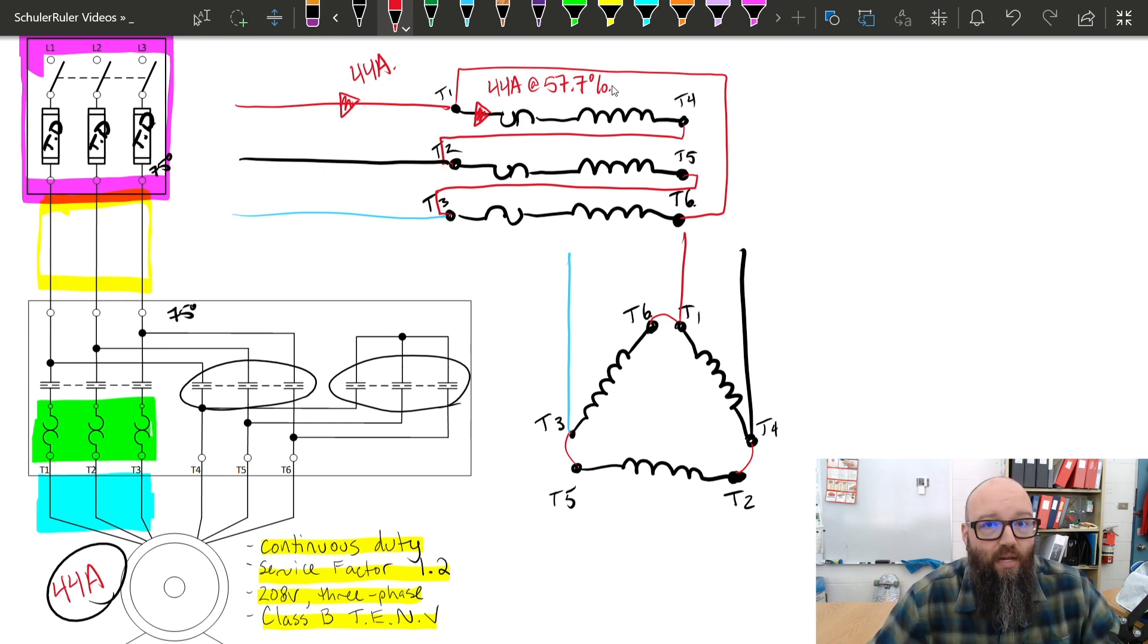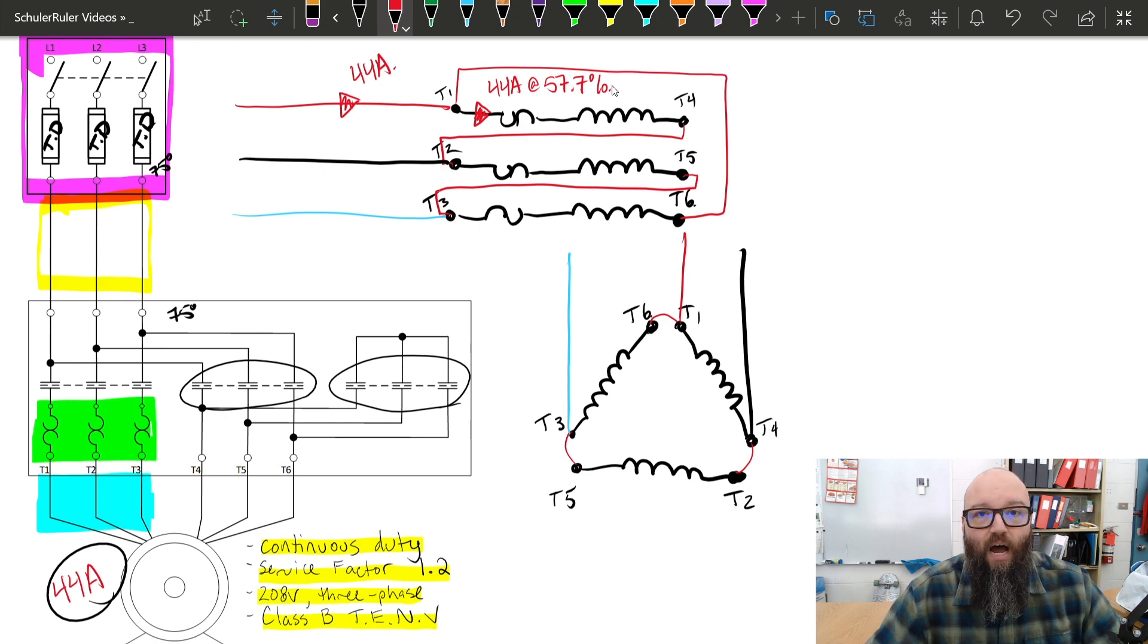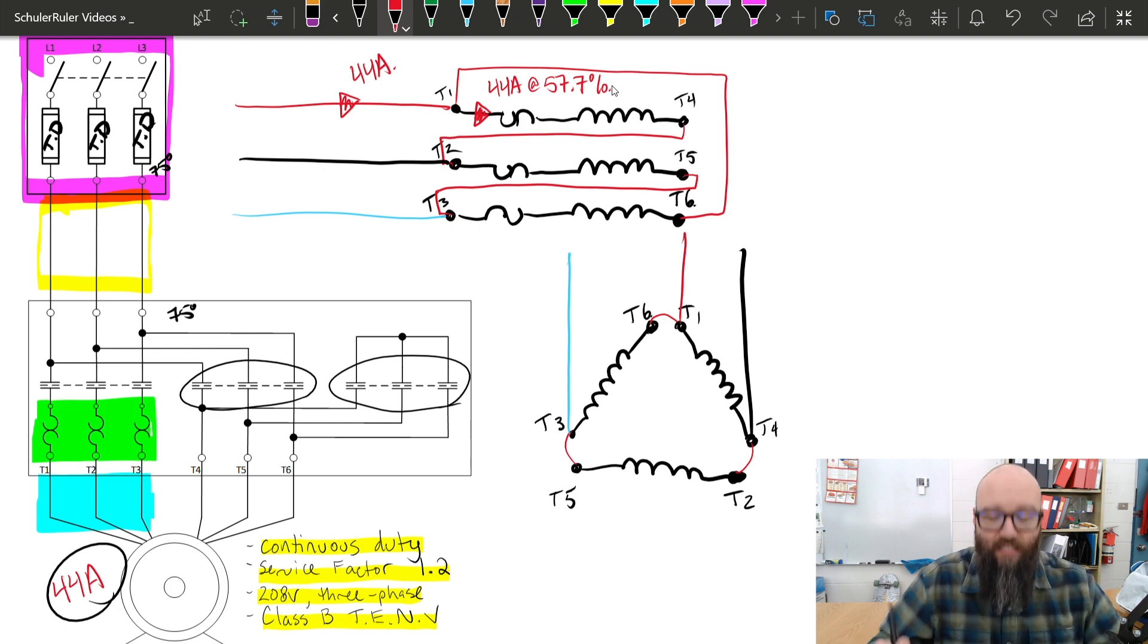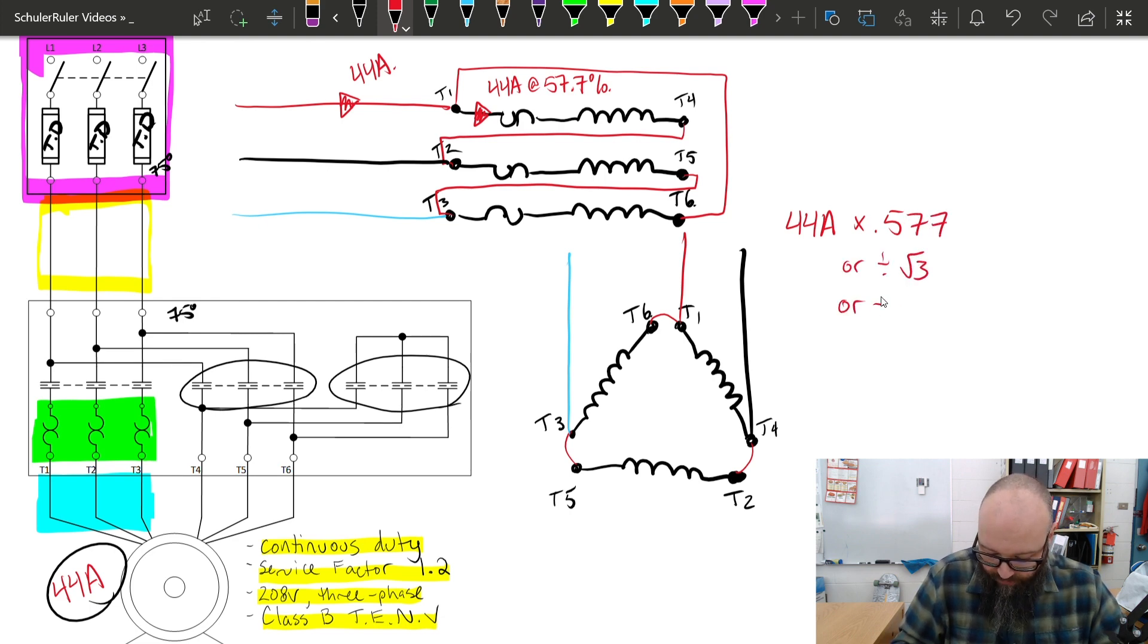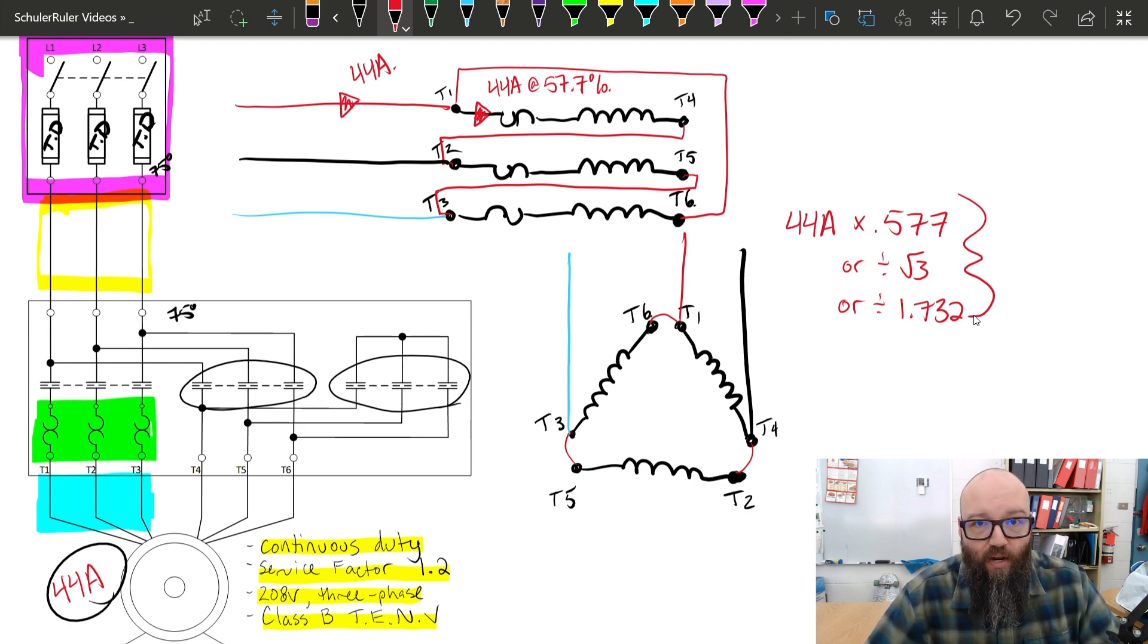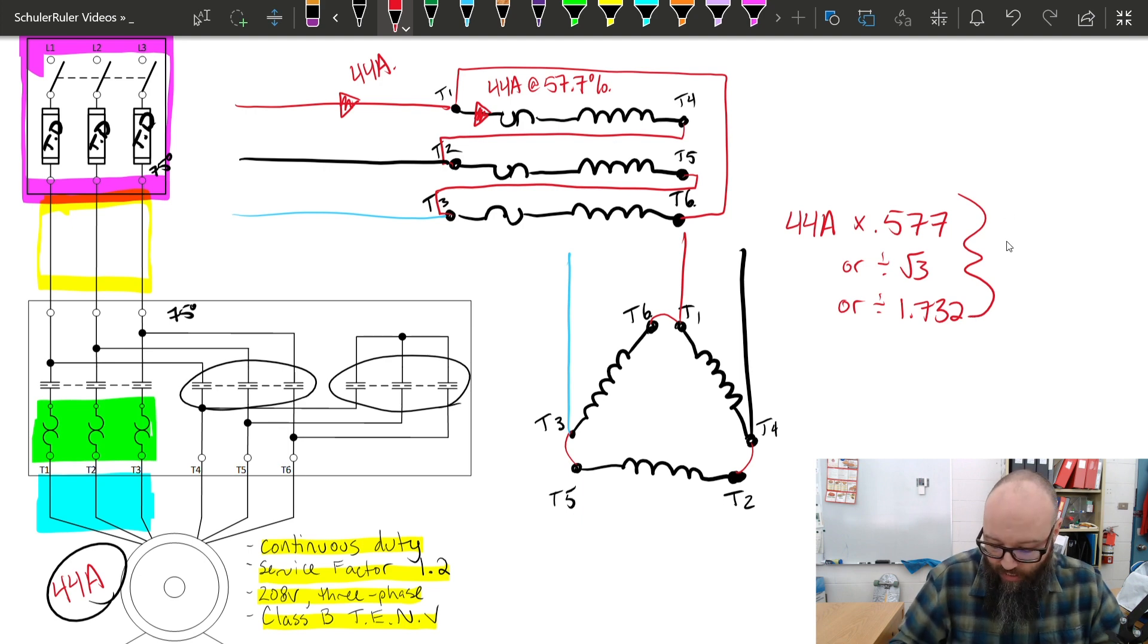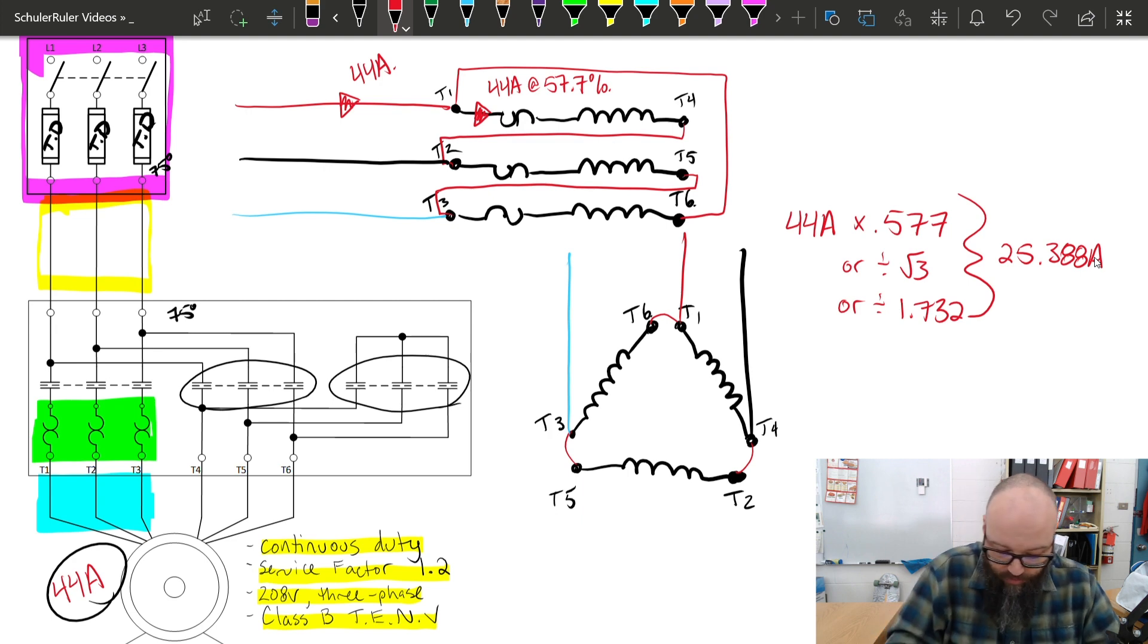Taking a look at 28.306 subrule two, it tells us that we're going to use the applicable percentage on the nameplate to determine the maximum overload settings. In this case, my overloads are only ever going to see 57.7% of that rated FLA. So, that's the first thing we have to do here before we ever go and size those overloads. I have to reduce that and find out what that phase current is. 44 amps times 0.577 or divided by root three or divided by 1.732. All of these are going to give us the same answer. They're going to give me the current that that overload is going to see during that run delta configuration, which is the highest that it's ever going to be exposed to. So, 44 times 0.577, we should see approximately 25.388 amps.